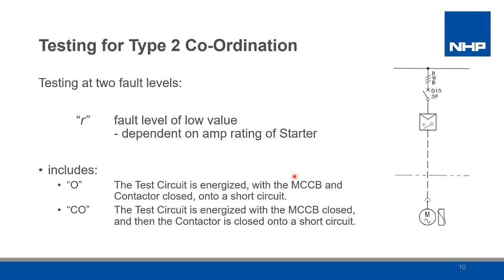Two short circuit tests are performed in sequence. The O test is performed with both MCCB and contactor closed, and then the test circuit is energized. As there is a short circuit on the load side of the contactor, the MCCB opens to protect the circuit. Then the CO test is performed with MCCB closed and test circuit energized. The contactor is remotely closed onto the fault and the MCCB opens to protect the circuit.